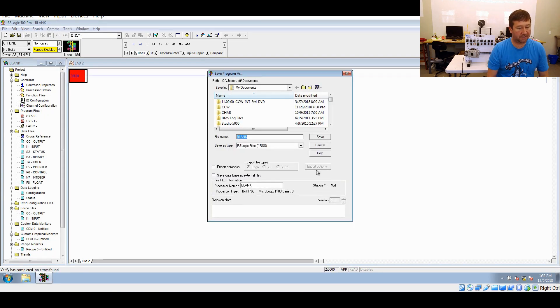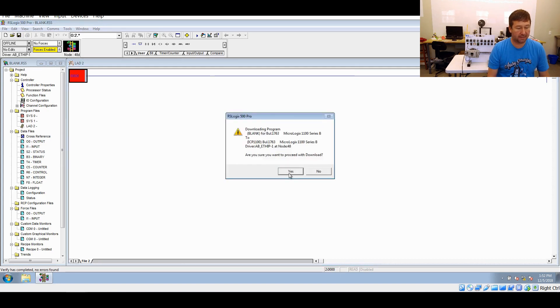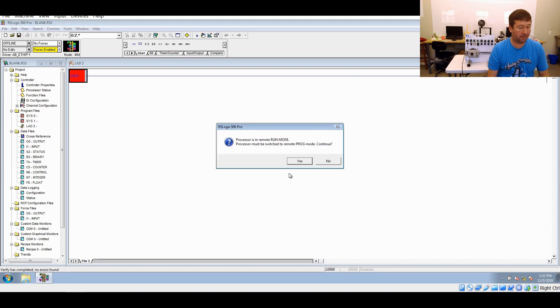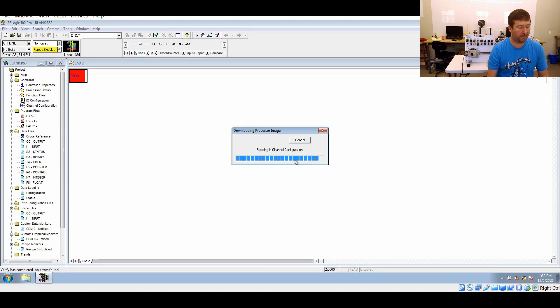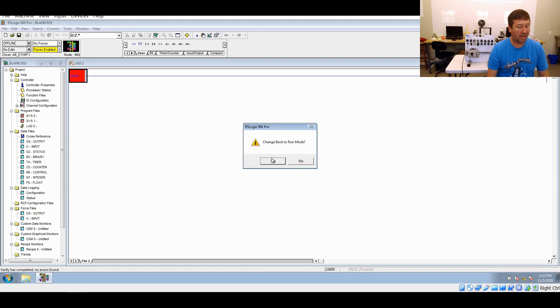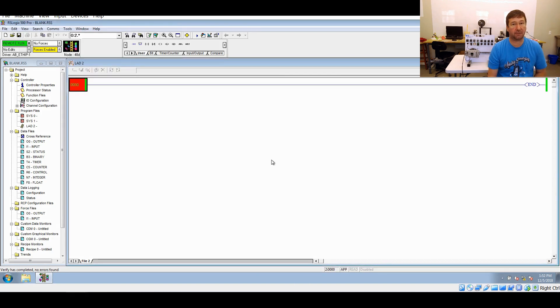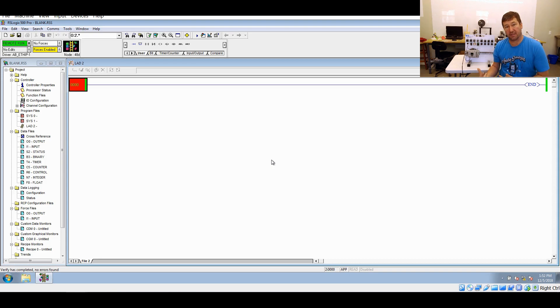We need to save our program before we can, so we're just going to save it as blank, and it's going to warn us that we're overriding the program that's in there with this program. We're going to switch from Run Mode to Program Mode, and now that it's done, we're going to switch back to Run Mode and go online. We are running a program in our PLC.